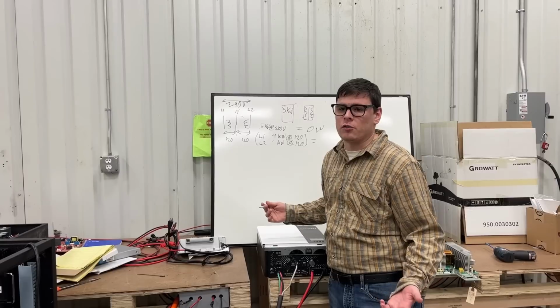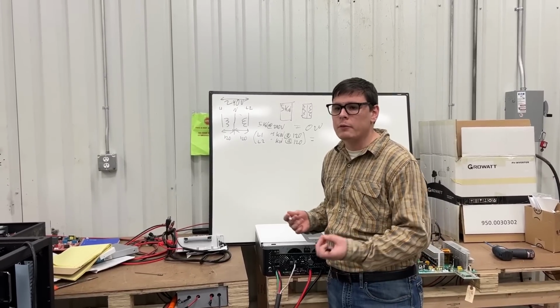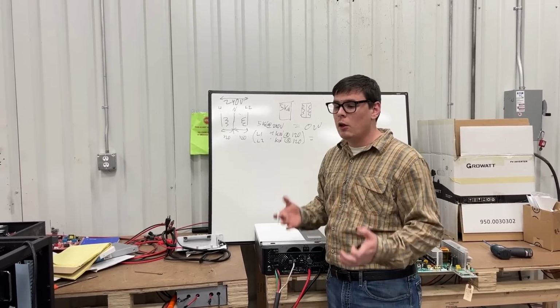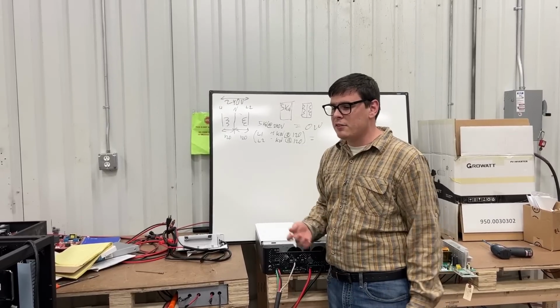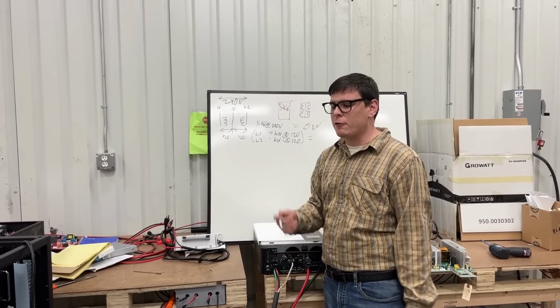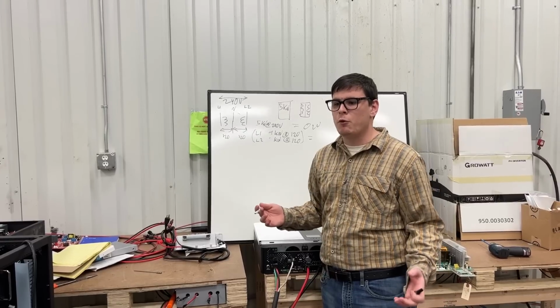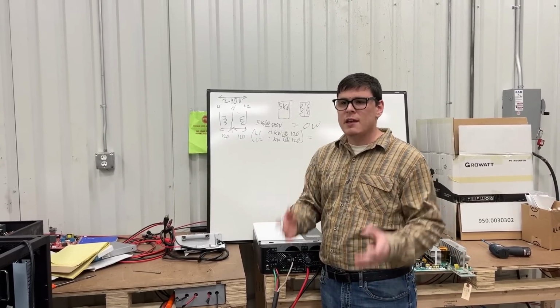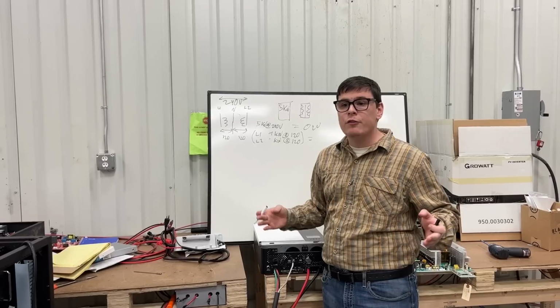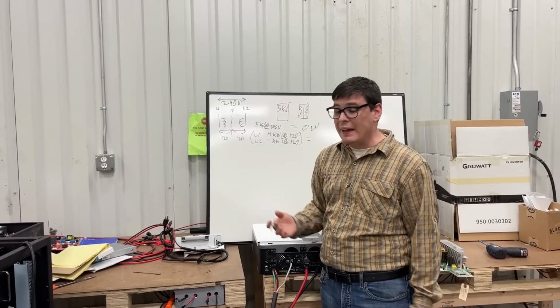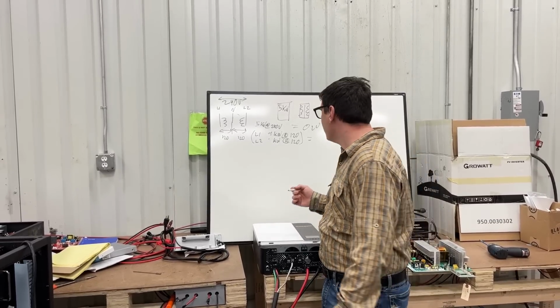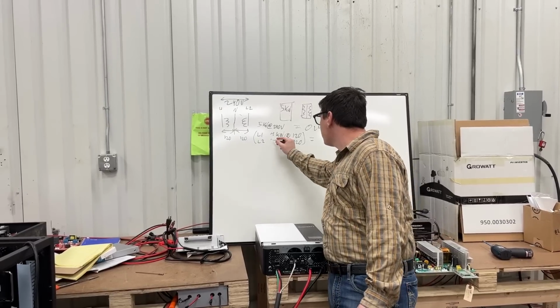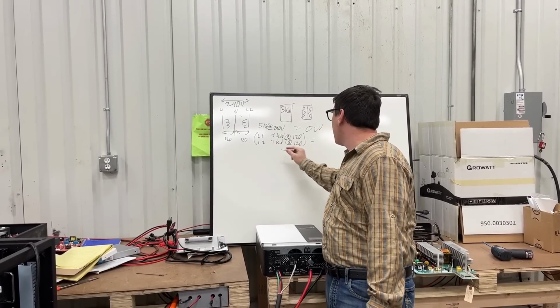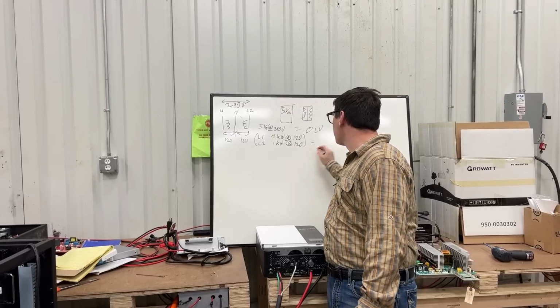And we're not talking motor surge here. We're talking something like resistive, some kind of steady load. I think I've seen some people that were running the transformers up to 240 degrees or something. So continuous heavy 120 volt loads, like heaters. And 4 versus 1, that means your differential is 3 instead of 1.